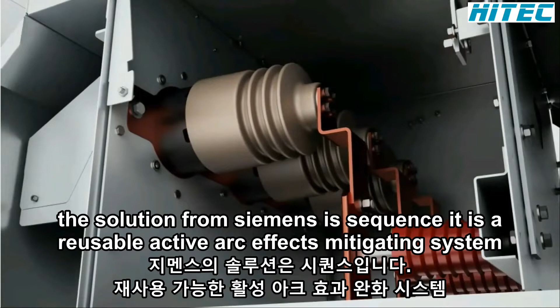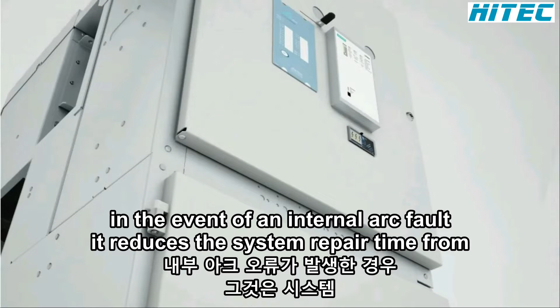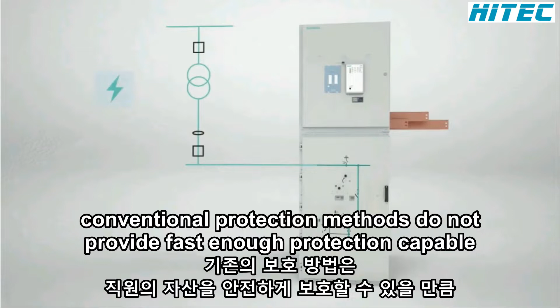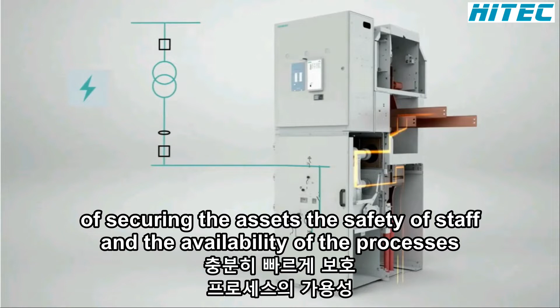The solution from Siemens is SIQuench. It is a reusable active arc effects mitigating system, quenching the internal arc in sub-cycle times. In the event of an internal arc fault, it reduces the system repair time from days and weeks to minutes and hours, resulting in drastically reduced economic losses. Conventional protection methods do not provide fast enough protection capable of securing the assets, the safety of staff, and the availability of the processes.